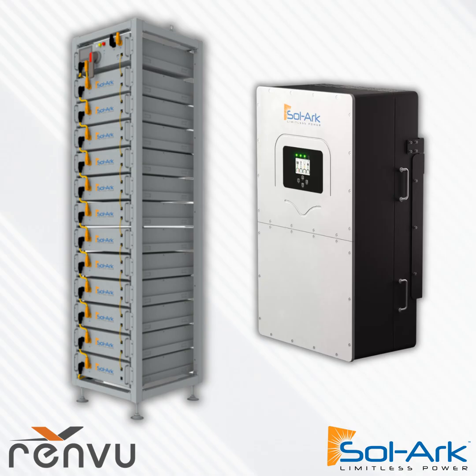We're going to talk real quick about some applications, some quick and easy applications. The first is adding batteries to an existing solar array with a commercial system. That's very easy with a Sol-Ark. You typically have in place with commercial solar a line side or supply side interconnection. And so you can undo that tap where that solar array is tapped onto the electric service and just drop in a Sol-Ark inverter in line. So in place of that tap, you lay in the conductors out to the transformer on the grid port of the Sol-Ark. You land any conductors running off to the service panel on the load port.